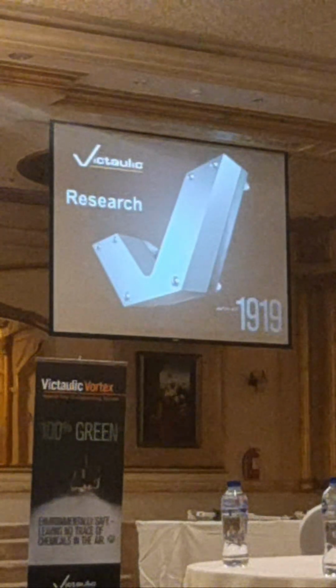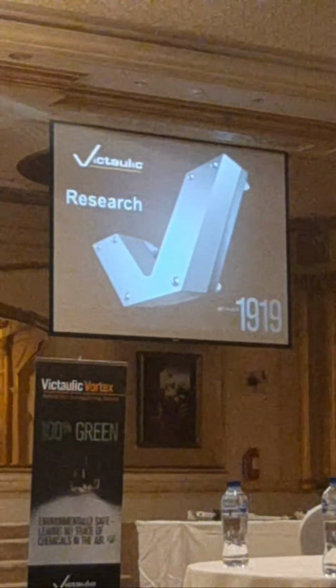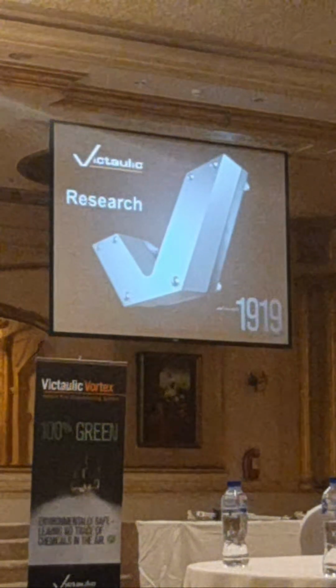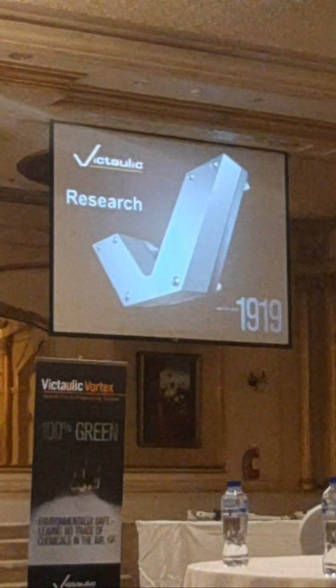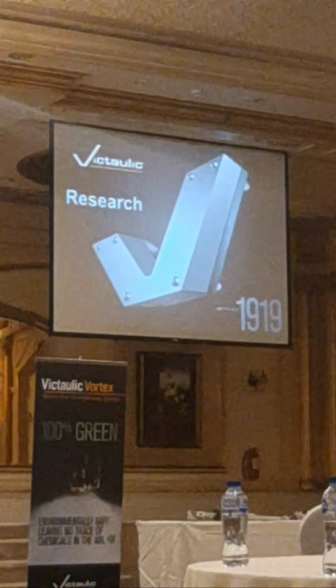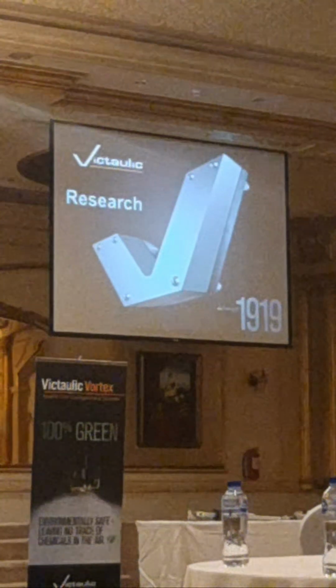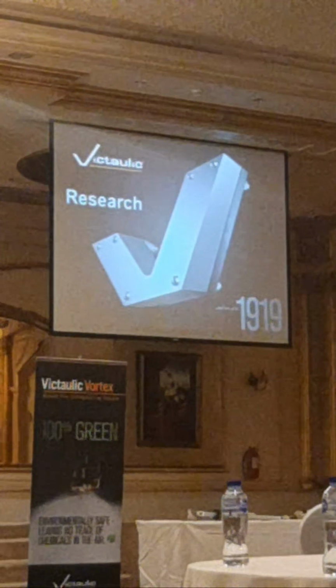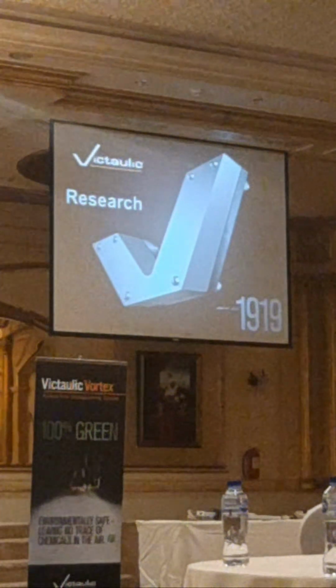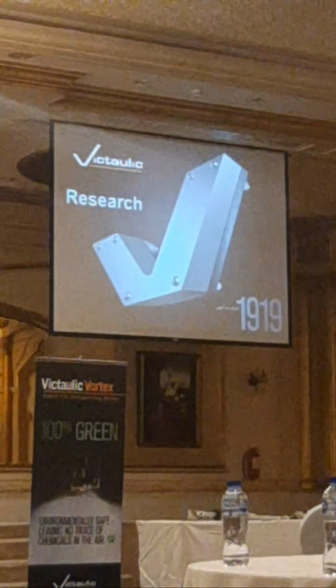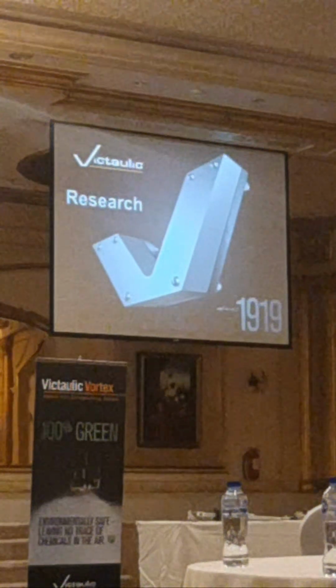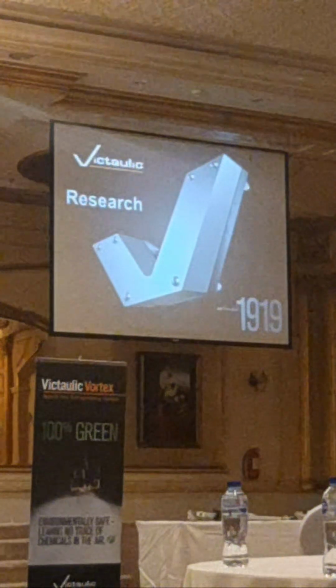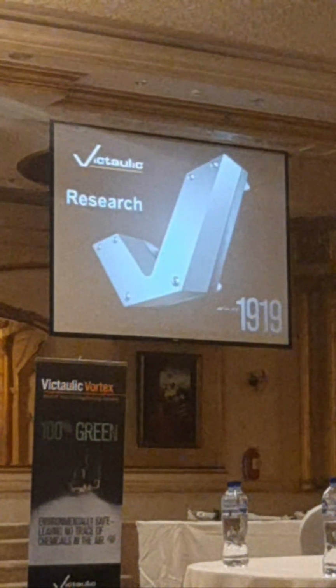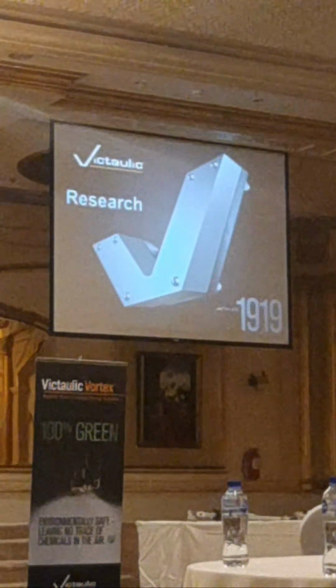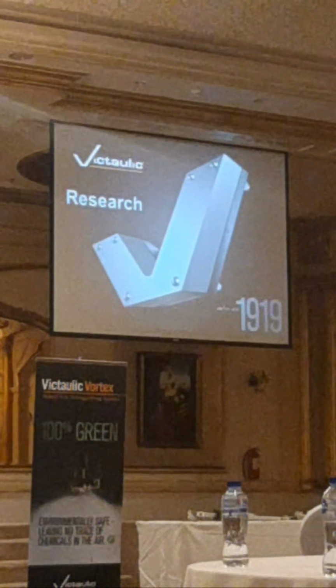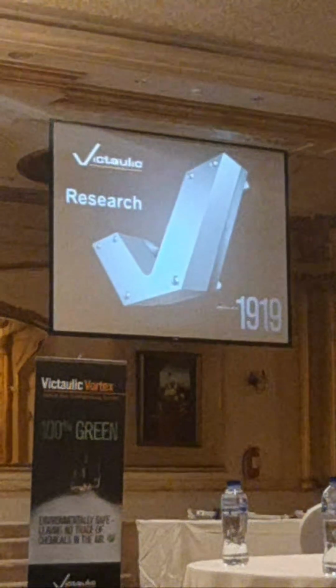It's rather going to be a hybrid factor, which is explained in our training. So if I say 0.307 now, that's not going to make sense to you. It's not a factor like you have in a sprinkler system, but we have to use it to decide water size and water demand. The amount of water is going to be decided on the application and the volume, not on something similar to a K factor. It's not the same design as a sprinkler system.